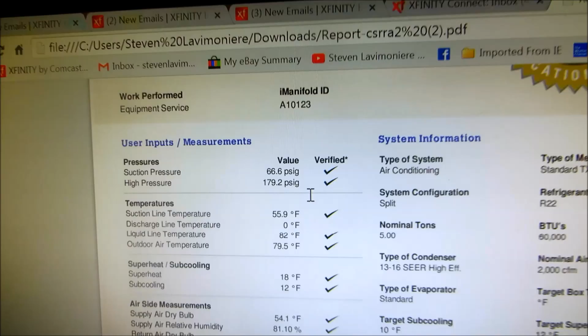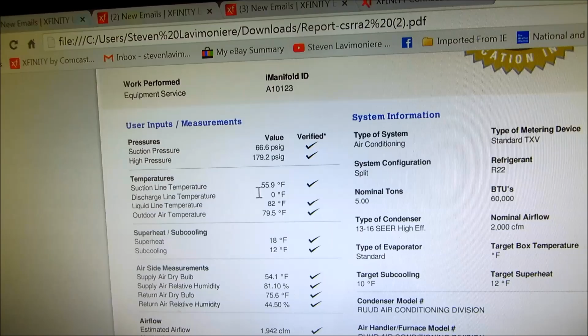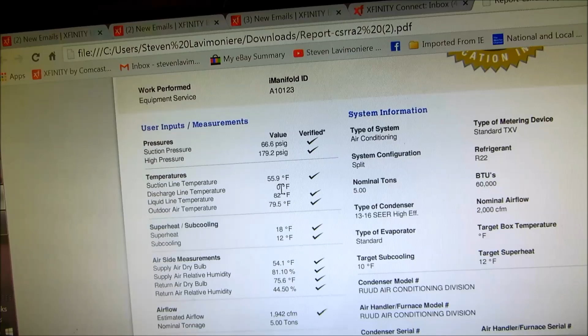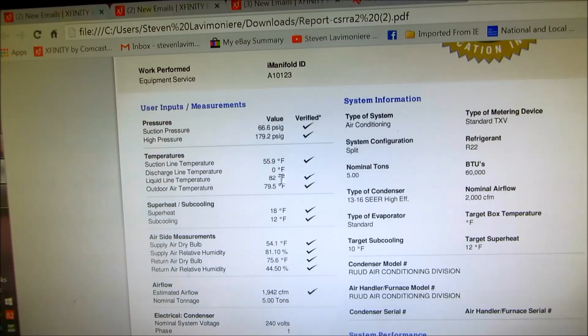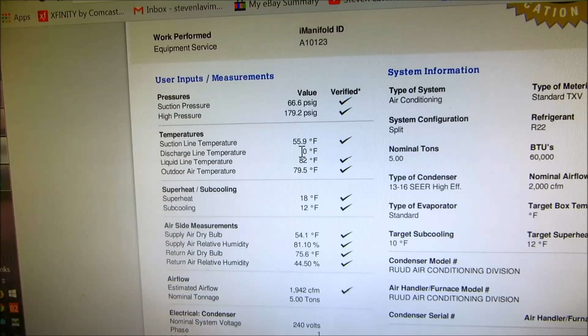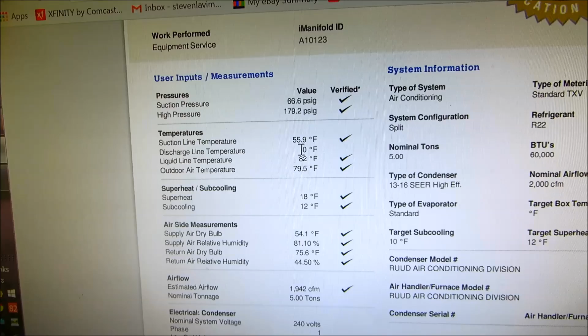Suction line, high temperature, high pressure, suction pressure, high pressure, suction line temperature, discharge line temperature 0 - that doesn't seem right. Oh, you know what that's for? That's for - they want you to take the discharge off the compressor, and I didn't hook that up. I gotta get a probe for that.